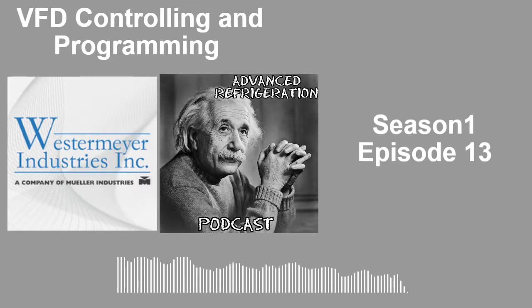Just to throw that out there, even though you're not ever going to see a VFD on a single system, you get a lot better control using a VFD. A VFD uses AC voltage and makes a sine wave, but it actually pulses what's called DC voltage. They do pulse width modulation. So it's pulsing DC voltage positive and negative to make a sine wave out of a whole bunch of little square waves. And that's how a VFD is doing its job.